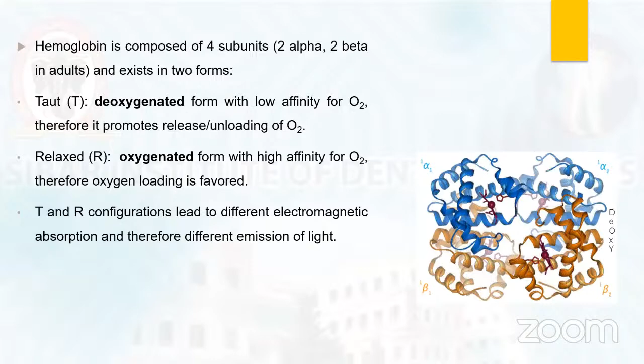So we have a tissue which consists of arterial blood, venous blood, and stationary tissue, and this is plotted against time. We obtain a ratio of the red light to the infrared light, and from it we get the oxygen saturation. In the arterial blood there is always an increase in blood volume as per the cardiac cycle. During systole there is an increase in the blood volume, whereas in the venous and capillary blood we don't have an increase in volume. So this volume increase also influences the amount of light that is transmitted.